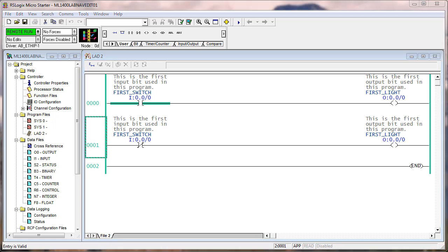And so that's what you're going to see. Last man wins. A couple more questions in the manual on this logic. What does the on-off state of the OTE output energize instruction tell us, and why does it not reflect the logic of these 2 rungs? That's because last man wins. Now this one looks okay. First rung is false and the output is on. So the true and the false is more important than the on and off. See here, rung 0 is true, but the output is off because rung 1 is false and turns the output off.